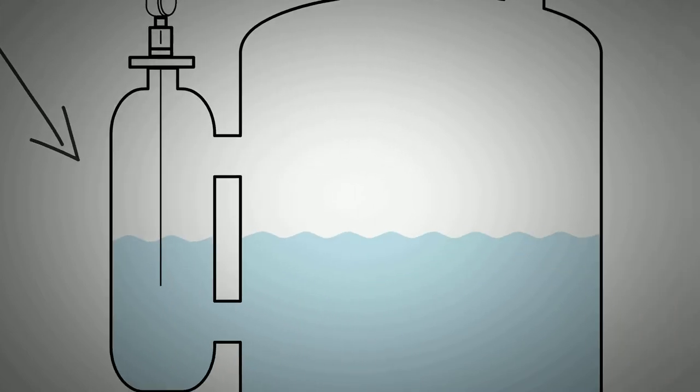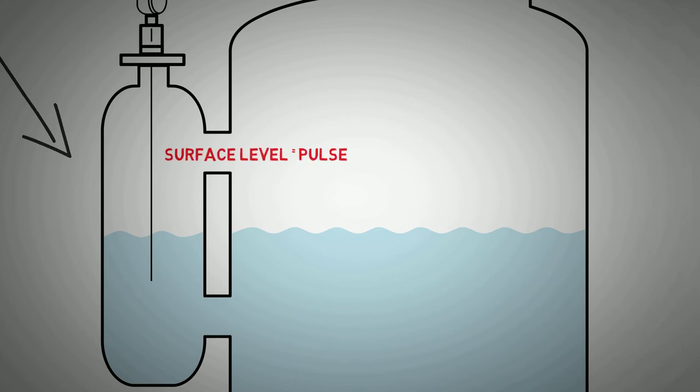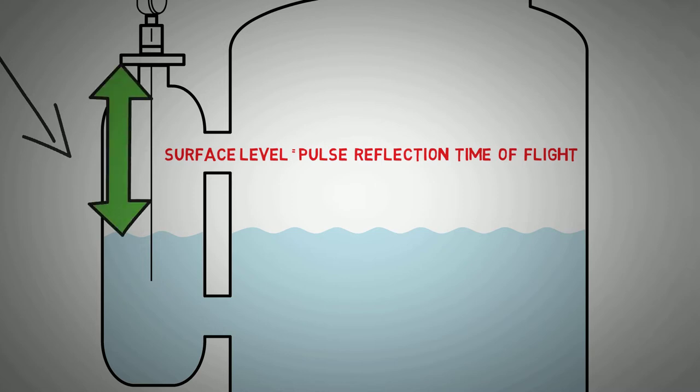The transmitter measures the time difference between the pulses being sent down the probe to being received and uses this to calculate the distance the media is from the probe and in turn can give a level measurement.